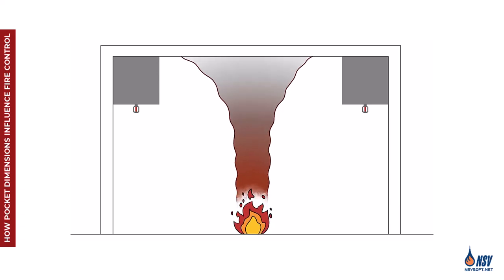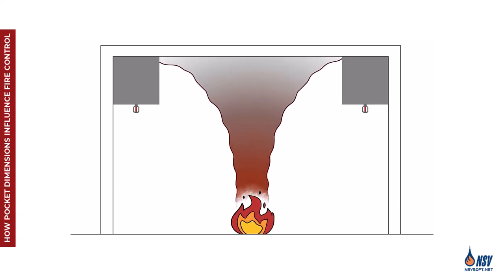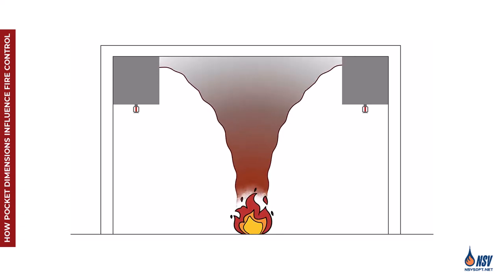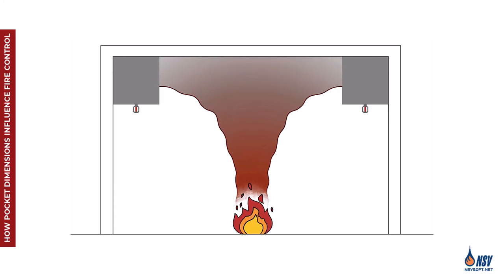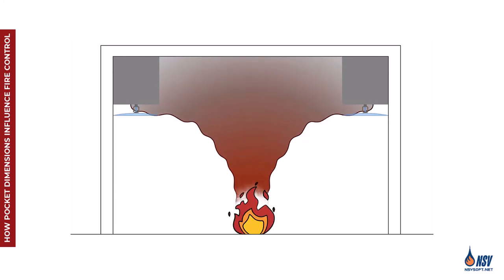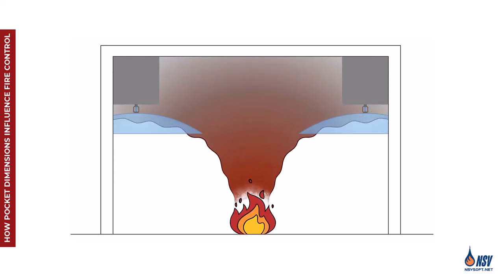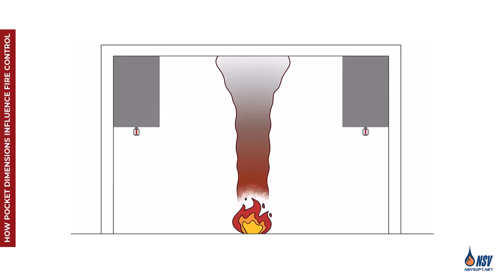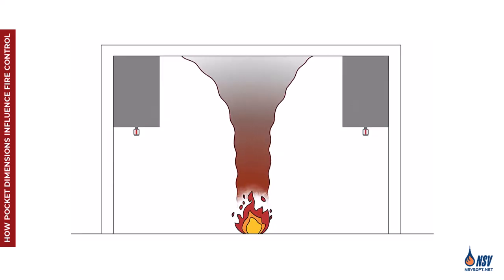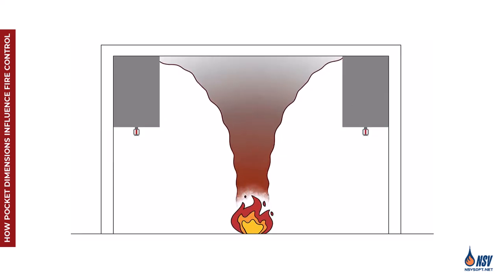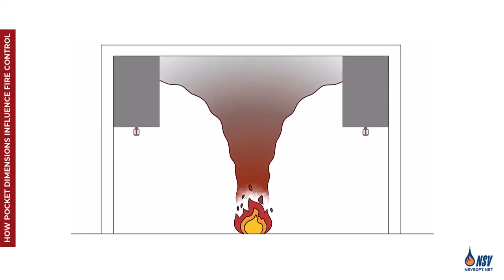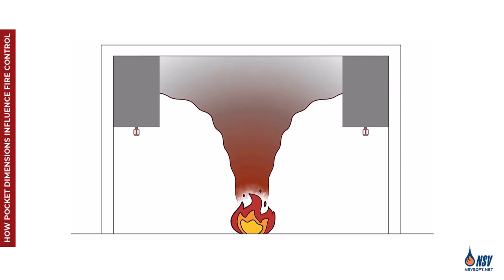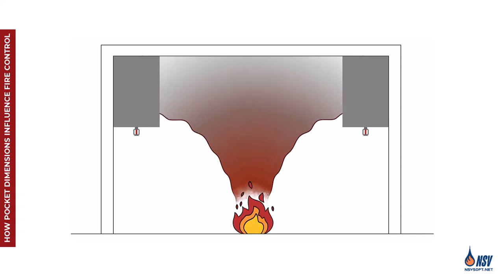When the depth or volume of a ceiling pocket is minimal, sprinklers installed at the lower ceiling level are generally able to respond promptly and control the fire effectively. In contrast, a more substantial pocket can trap heat, delaying sprinkler activation and increasing the risk of uncontrolled fire growth.